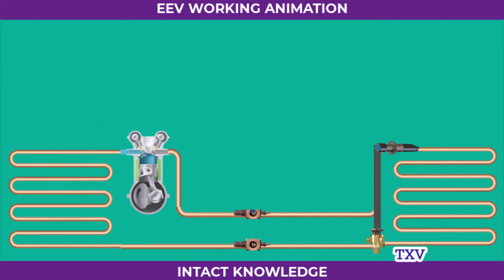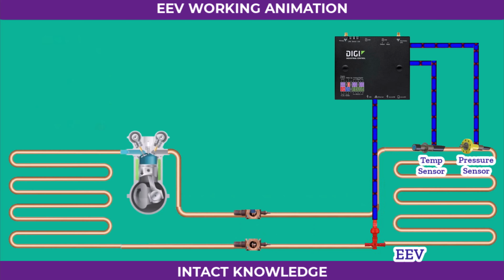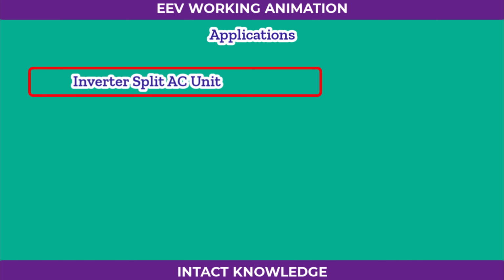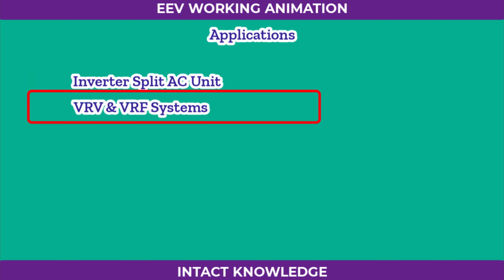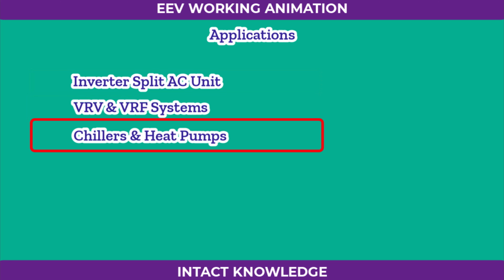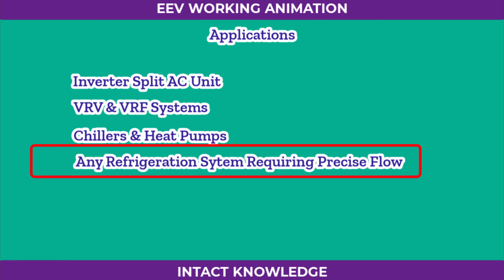For instance, imagine that during the night, as the temperature drops, your system's cooling demand suddenly decreases. A TXV takes time to adjust to this change, but an EEV instantly receives live data from its sensors and corrects the refrigerant flow within seconds, avoiding both overfeeding and starving conditions. Applications: inverter split AC units, VRV/VRF systems, chillers, heat pumps, and any refrigeration system requiring precise flow regulation.